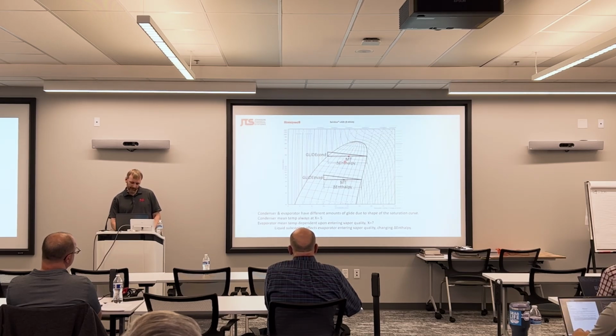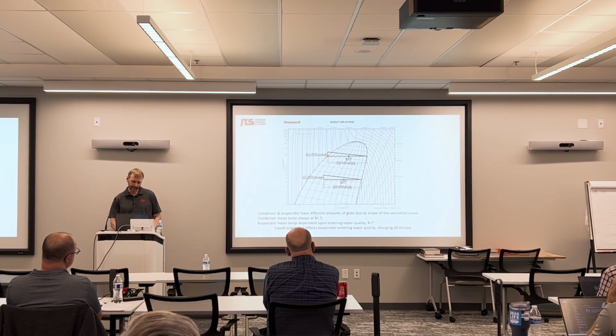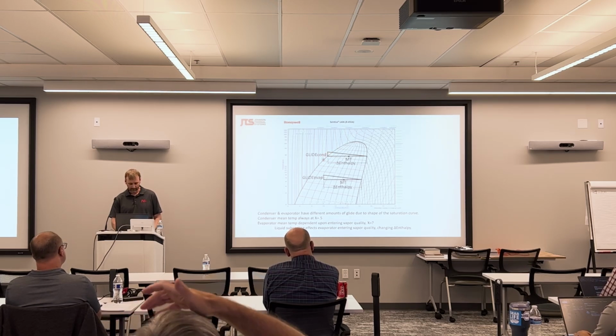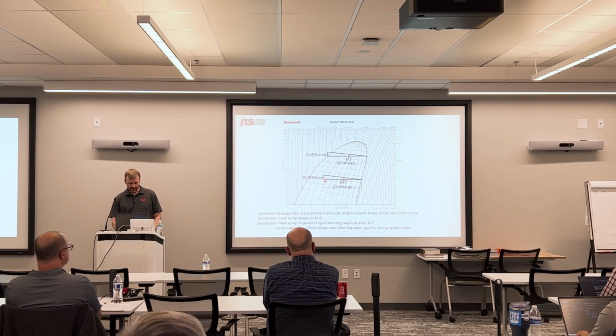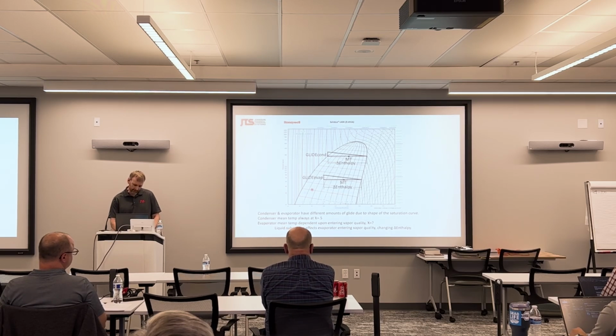So to map out both the condenser and the evaporator, the amount of glide that's generated through each is very much dependent upon the change of enthalpy. A condenser will always condense from the dew point to the bubble point. It travels all the way across the vapor dome. Your evaporator only travels partially across the vapor dome. It's very much related to what your liquid temperature is and what your condensing temperature is. So your change in enthalpy through the evaporator, again, could be anywhere from an evaporator vapor quality of 0.25 to 0.5. But something else that's interesting here, if you look at these lines going across, these are your lines of constant temperature. They're at a constant slope.